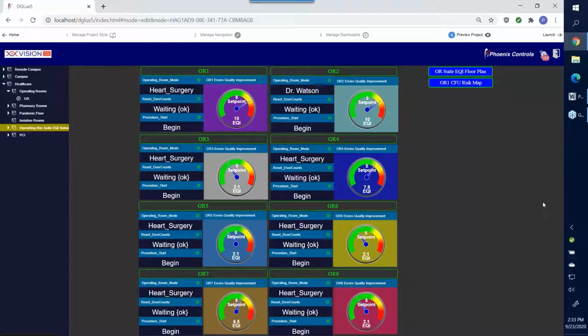If you take all the parameters associated with a particular operating room, they can be put into an algorithm which gets you a number known as an EQI number. The EQI takes all the parameters, weighted, to determine whether this is a safe operating room or not. This gives an example where you might be looking at 8 ORs trying to determine their ability and their level of EQI, a rating for cleanliness within an operating room.